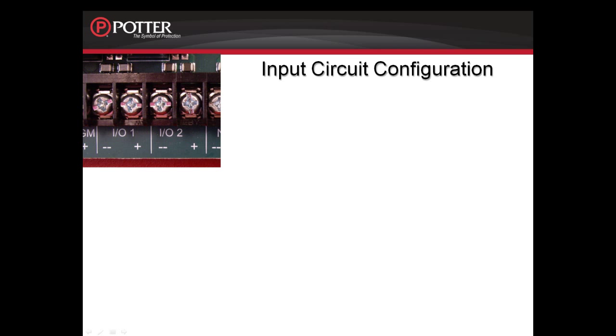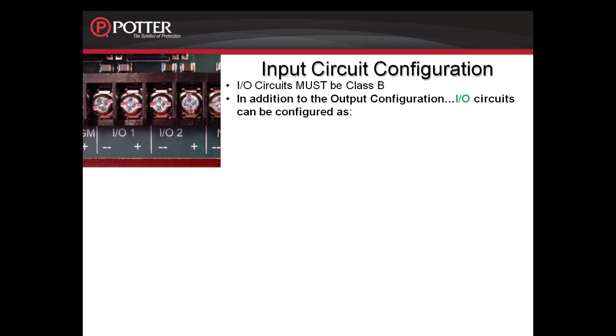When working with the I/O circuits on the fire alarm control panel, they must be wired Class B. When configuring the circuit as an input, we are monitoring a dry contact input. Through the software, you decide what that contact input is monitoring. Your options are as follows.